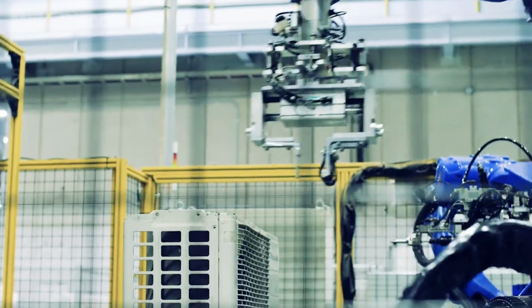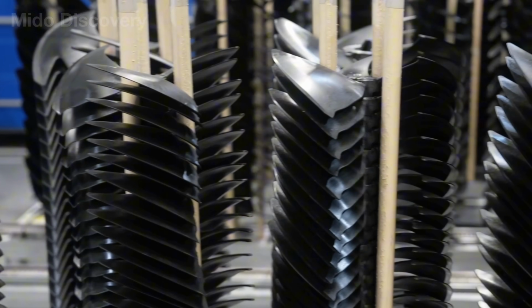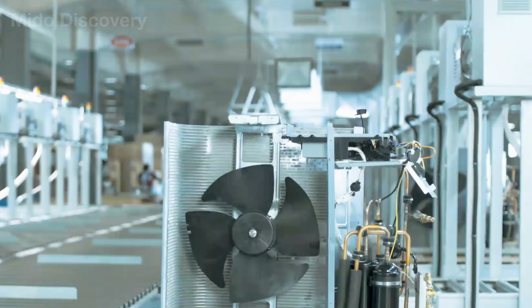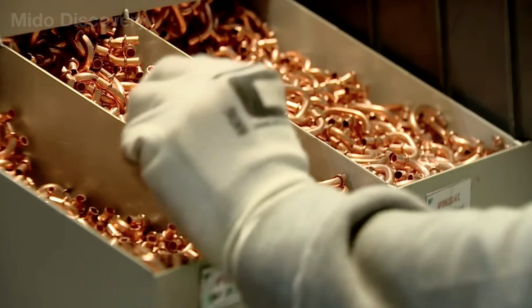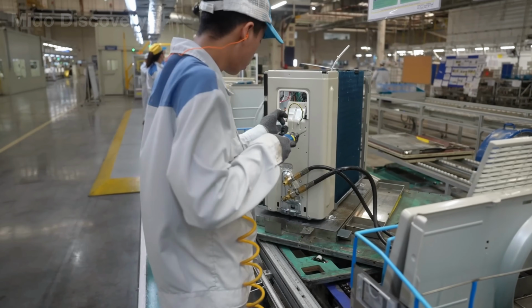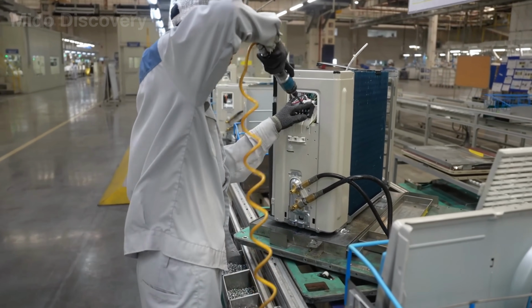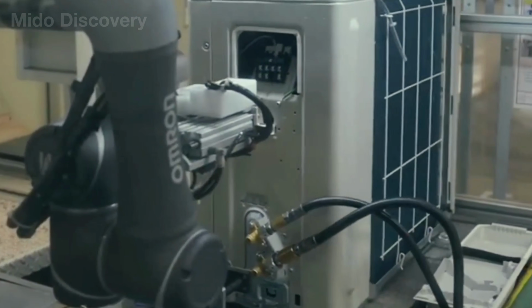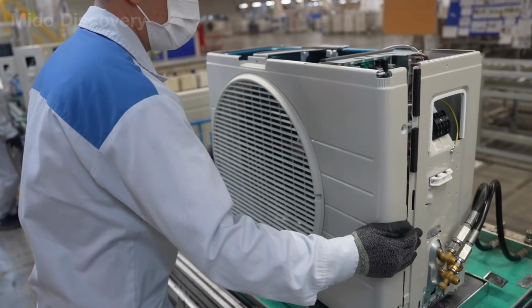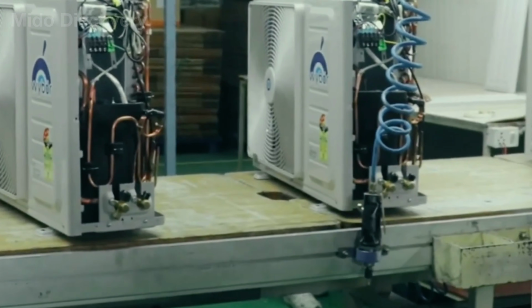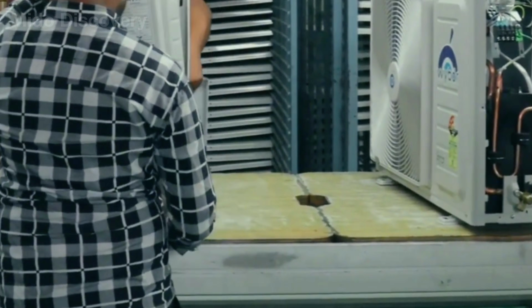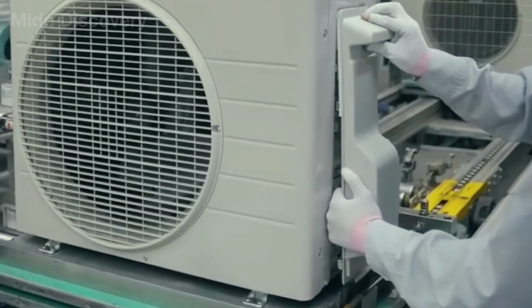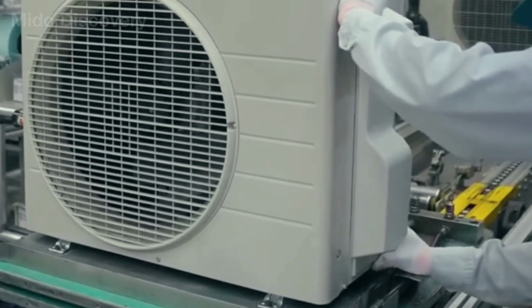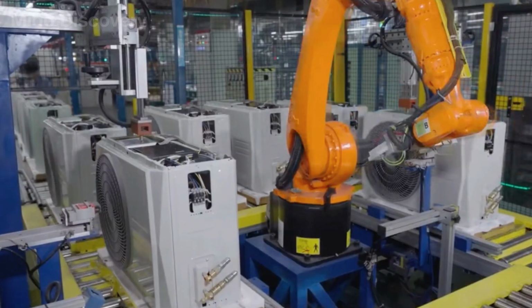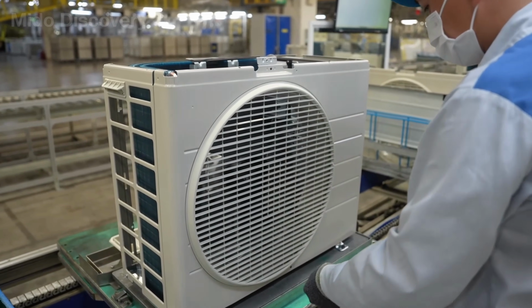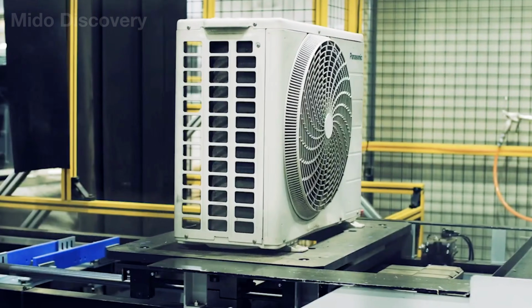Next, the condenser coil, fan motor, fan blade, partition panel, and electrical enclosure are installed around the compressor. Depending on the design, workers may also add a reversing valve, expansion device, accumulator, and pressure and temperature sensors. The copper tubing is bent, carefully aligned, and brazed shut, connecting the components into one continuous closed loop. Retaining clamps are added to prevent the tubes from striking the cabinet during vibration. Finally, wires from the compressor, fan, and sensors are connected to the control board. At this point, the outdoor unit is ready to receive heat from the room and release it into the outside air.